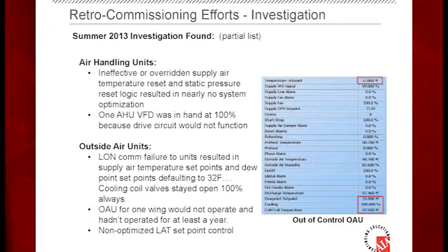When we actually commissioned the outside air units, we did our limited testing and we put them in. They're factory controllers, and they were all working like the factory said they were supposed to. At the time we left them, they were also talking to the BAS, and the BAS was telling them when to come on and off. It was doing what it was supposed to be doing.